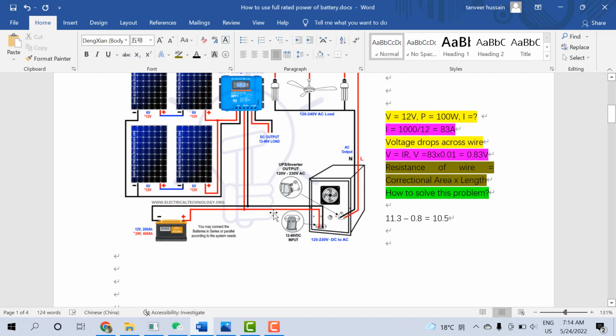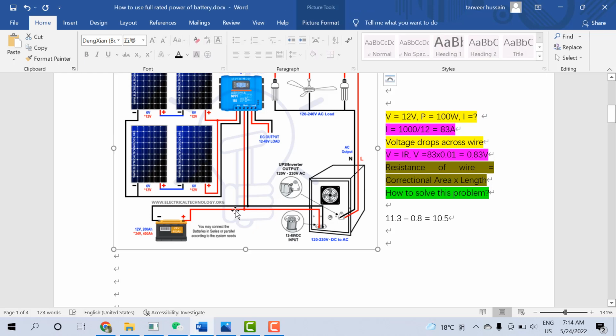You should first check the maximum current flow through this wire and select a cable that can support such high ampere currents. Some wires can support high current but still have a minor resistance, and due to that resistance, you cannot use your maximum battery capacity. So make sure the length between the inverter and battery is small.